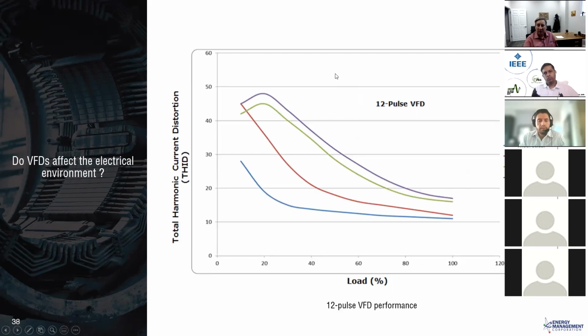I wrote a white paper quite a few years ago, and Craig Hartman, our great PE engineer that passed away from leukemia a while back, updated it a year or two ago. We went through a fairly extensive dissertation on harmonics, covering all the different ways you can mitigate harmonics with passive harmonic filters. Back in '88, we received a patent for one of the early hybrid passive harmonic filters. We thought that technology would only be valid for a few years until it was all solid state electronics. Still today, most of our jobs call for passive filters because the expense is so much lower.